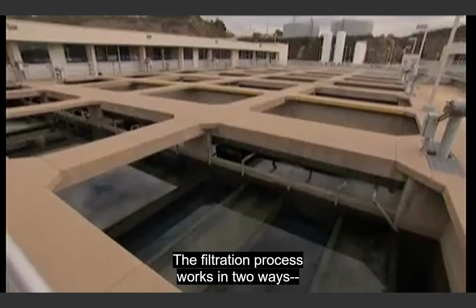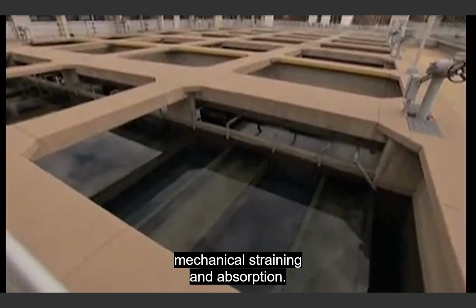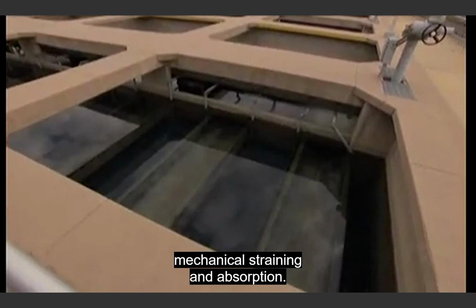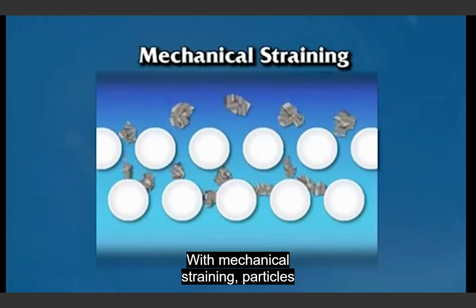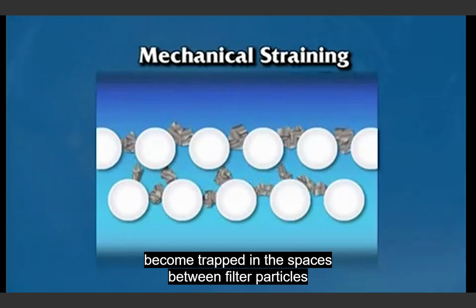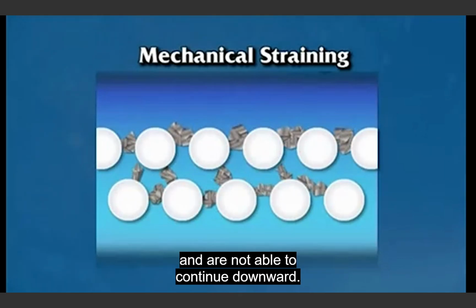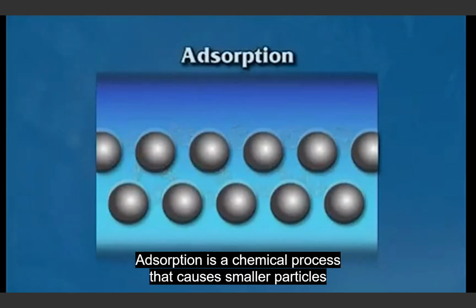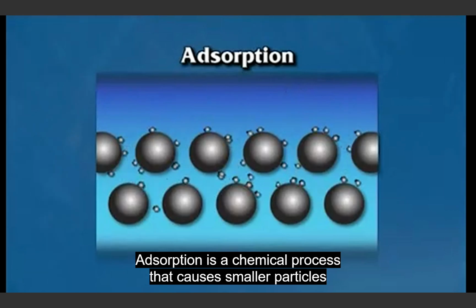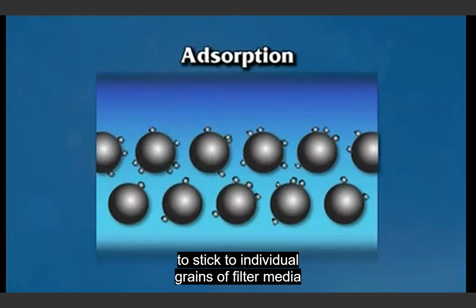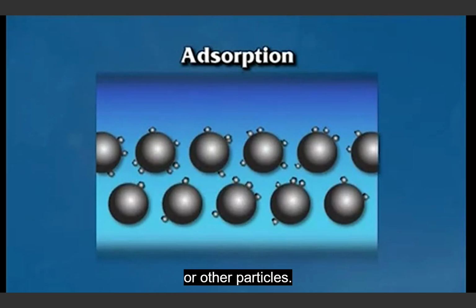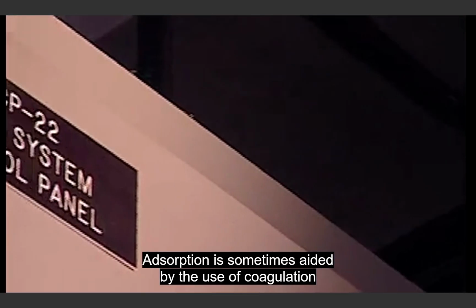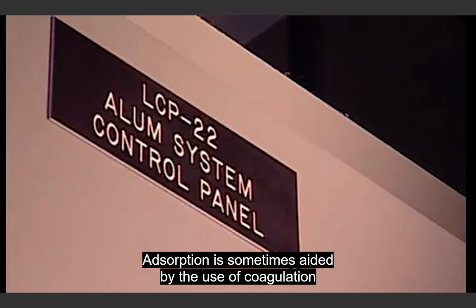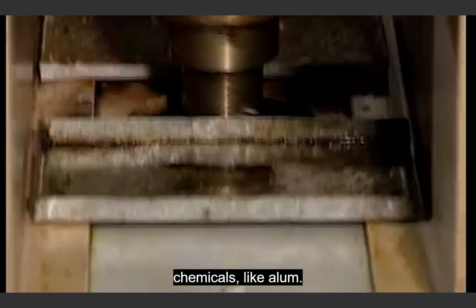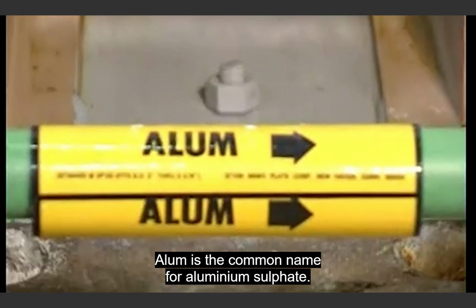The filtration process works in two ways: mechanical straining and adsorption. With mechanical straining, particles become trapped in the spaces between filter particles and are not able to continue downward. Adsorption is a chemical process that causes smaller particles to stick to individual grains of filter media or other particles. Adsorption is sometimes aided by the use of coagulation chemicals like alum. Alum is the common name for aluminum sulfate.